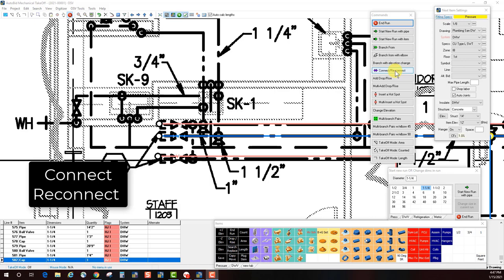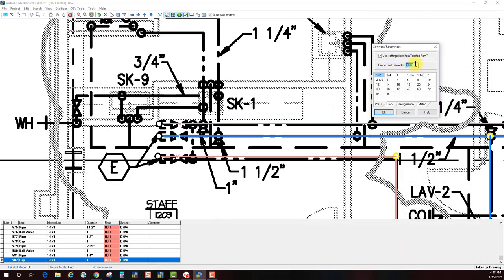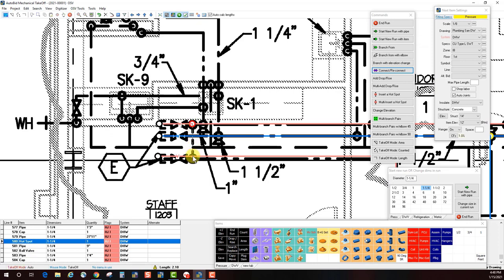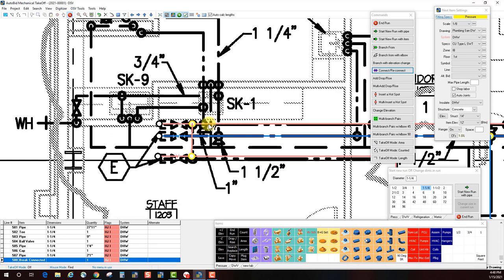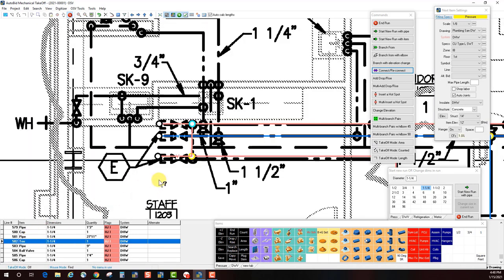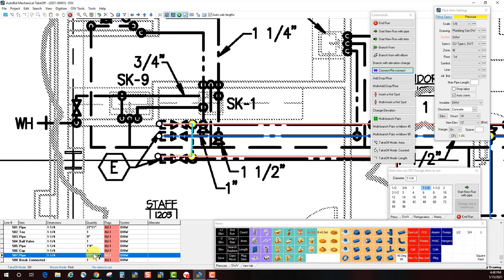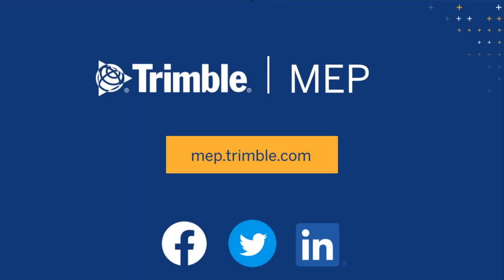The Connect Reconnect command is used when a pipe needs to connect from one pipe to another. In this scenario, I need to connect the inch and a quarter hot water recirculation to the inch and a quarter hot water line. Using Connect Reconnect, I verify the size — inch and a quarter — click OK, then click from one pipe to the other. It inserted a T in one line, a T in the other line, and a length of pipe between them — in this case two feet one inch. We hope you enjoyed this video — see what's next in our product tips playlist or visit mep.trimble.com.